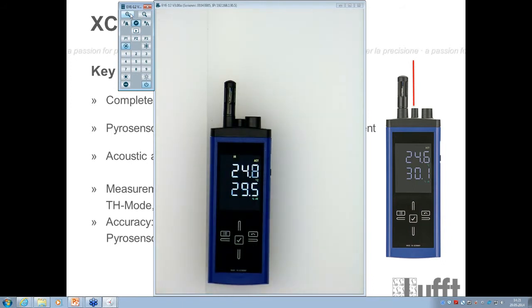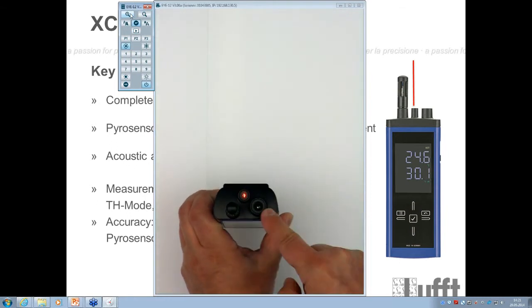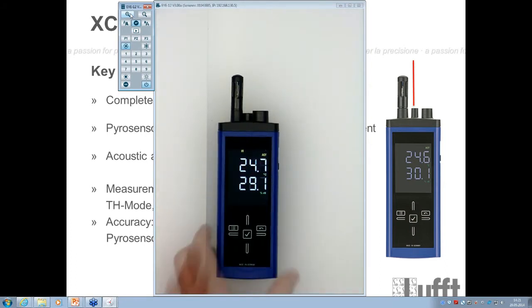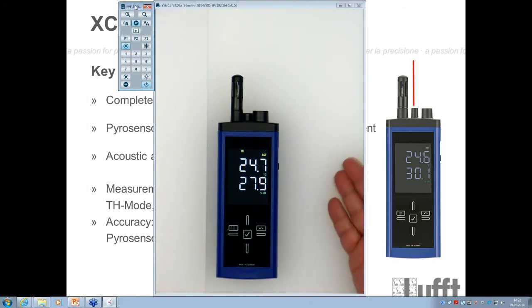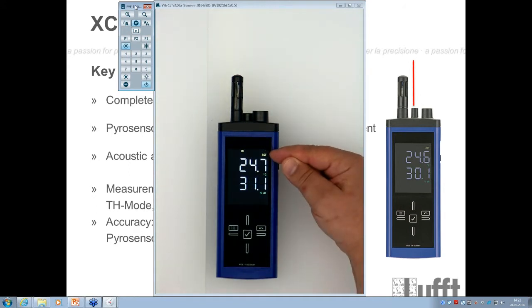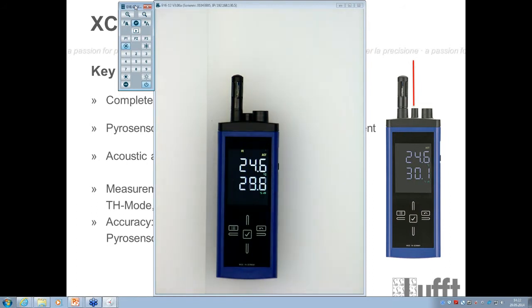And if IR is active, you will see it, I will show you. You see the laser is active and the pyro is active. And you will see now that, because now my sensor is measuring the wall temperature, because it's pointing to the wall, the wall temperature is 24.7 degrees here. It's the actual value. You can also switch between actual, hold, min, max, and average.